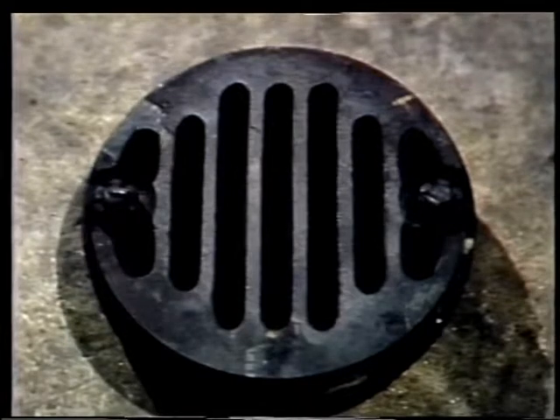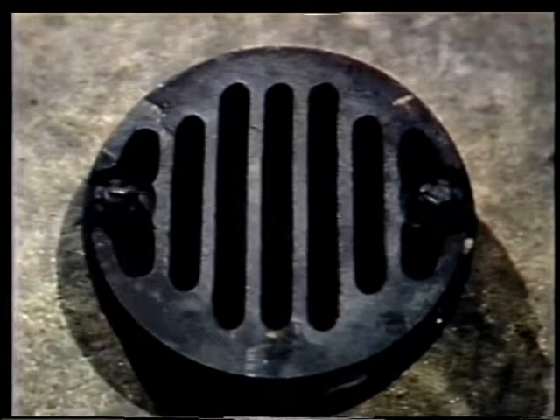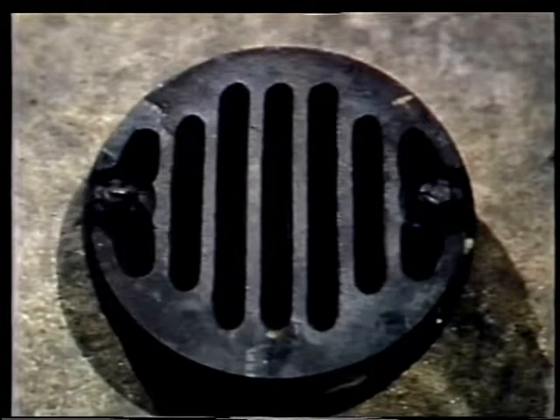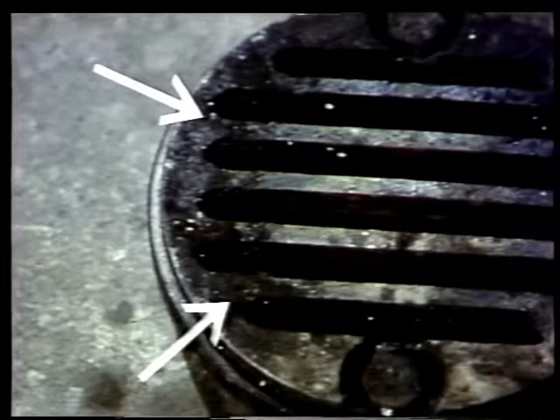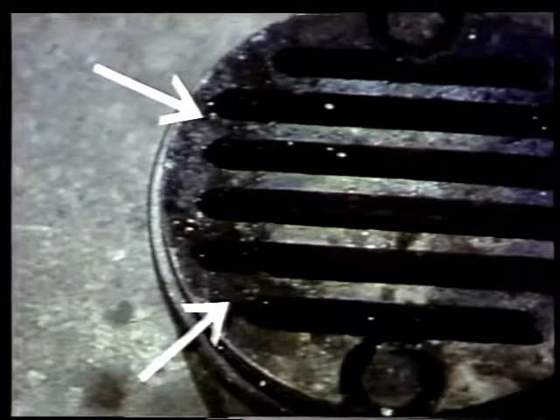When cleaning the surfaces, check for excessive carbon buildup. The carbon should be in a thin, even layer. Now, if you notice any chunks of carbon, too much oil may be getting into the cylinder. If this is the problem, the cylinder lubricator should be adjusted to reduce the oil flow when the compressor is started up again. This might also be caused by too much heat in the affected area. If this is the case, the flow of cooling water through the water jackets should be increased.